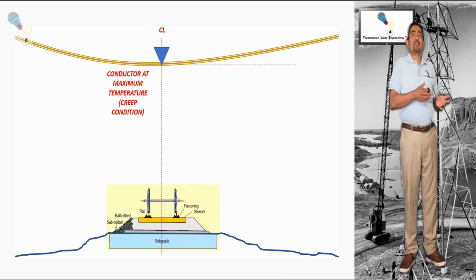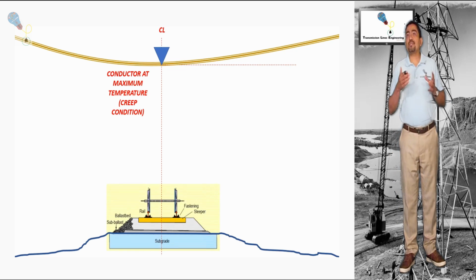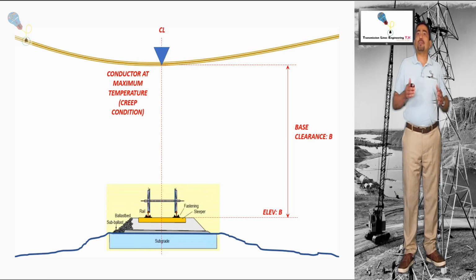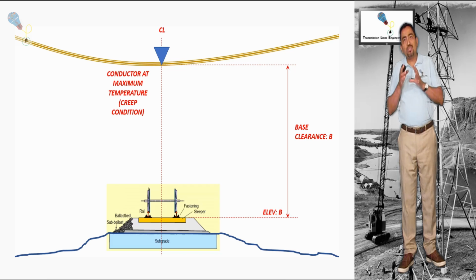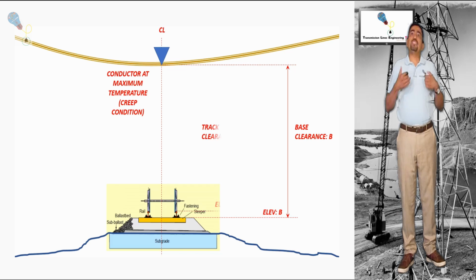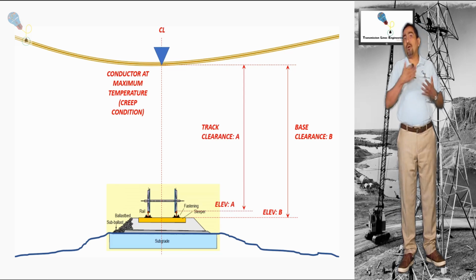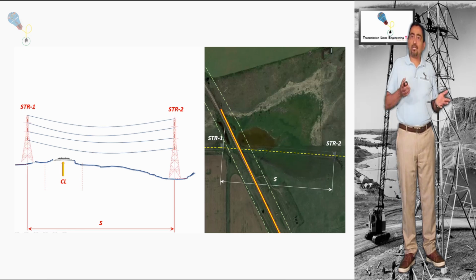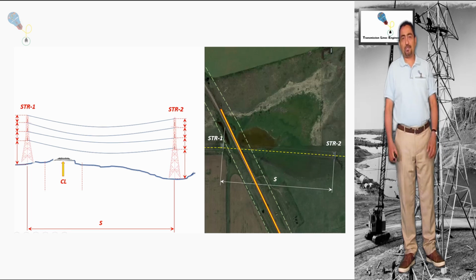The railway tracks are built on a compacted surface which is above the level of the natural terrain, and this small detail can become the difference between giving a permit or not, or what could be worse, putting at risk the vertical clearances from the train cars towards the energized cables.